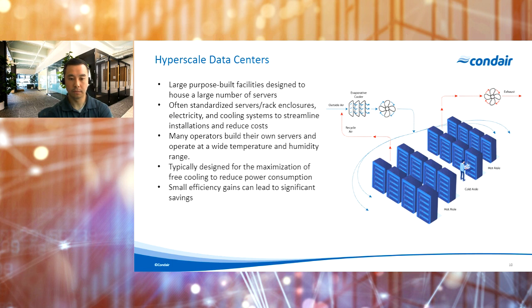In this type of facility, it's more and more common to see the owner and the operator design really every aspect of this facility. So the building layout, cooling systems, the electrical systems, and really increasingly more, even the IT equipment operating inside. So having this really full holistic design can help streamline the operation and allow for a far more aggressive set of operating conditions and lower resource consumption. Just given public announcements, many of the large data center hyperscale operators at this point are operating their IT inlet temperatures close to or above 90 degrees Fahrenheit.